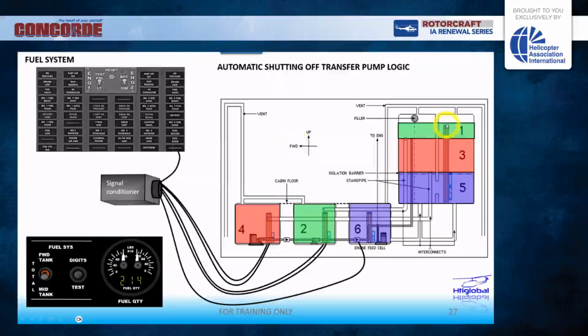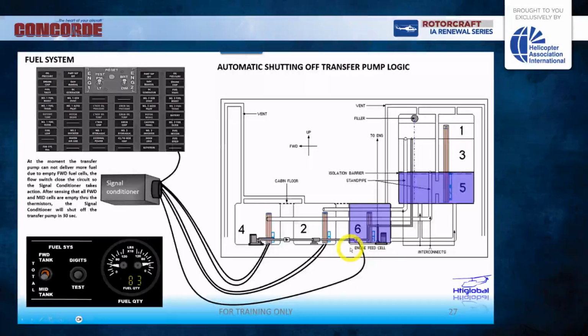So let's start flying the helicopter. We're going to burn the fuel here, then burn this one. At this point, the thermistors of the transfer and mid cells are empty, dry. We continue flying. Now when we get to this point, the transfer pump is sucking air and fuel. What happens with the flow switch? The gate starts closing and closes the micro switch. When that happens, it gives a signal that the transfer pump isn't working. Remember, this happens very fast, I'm trying to explain it, I can't go that quickly, but this is what's going on in the system.